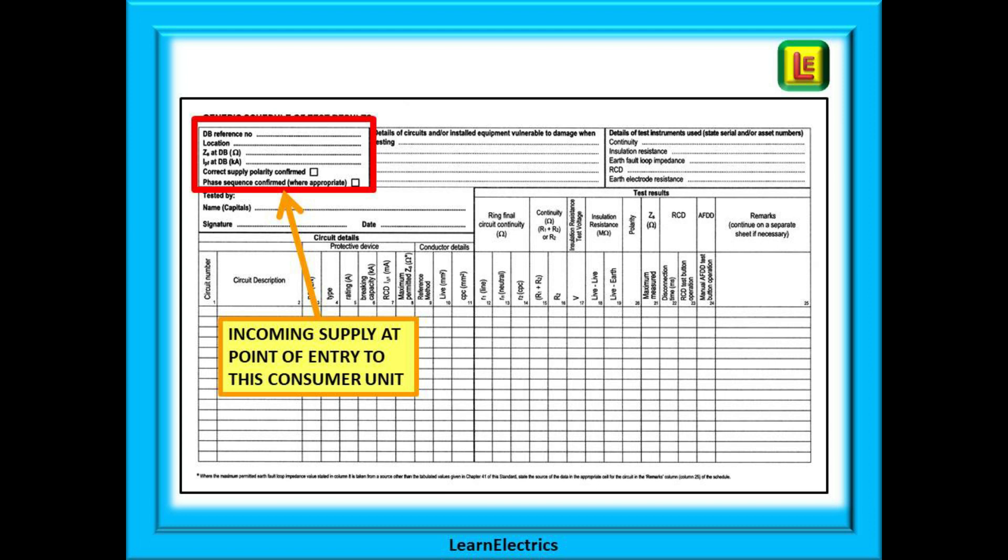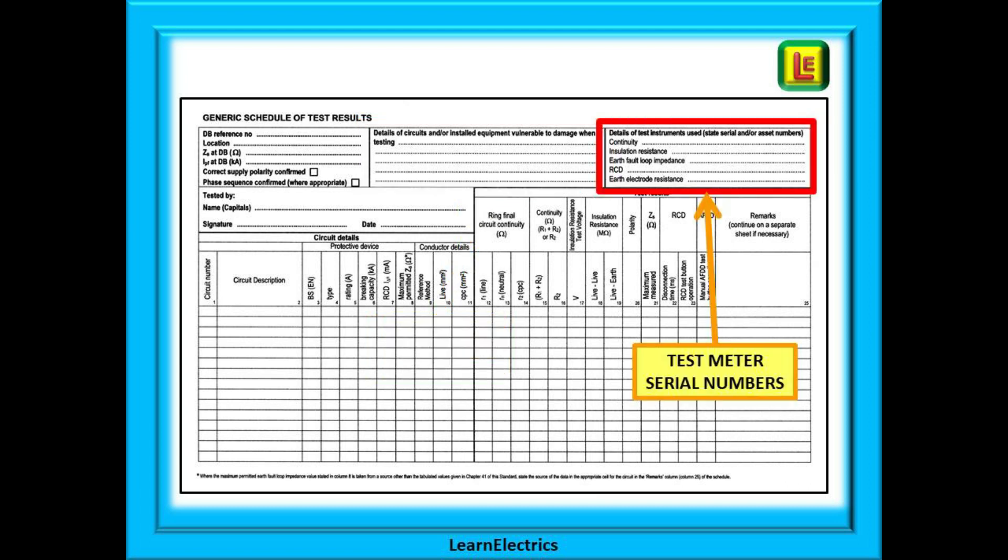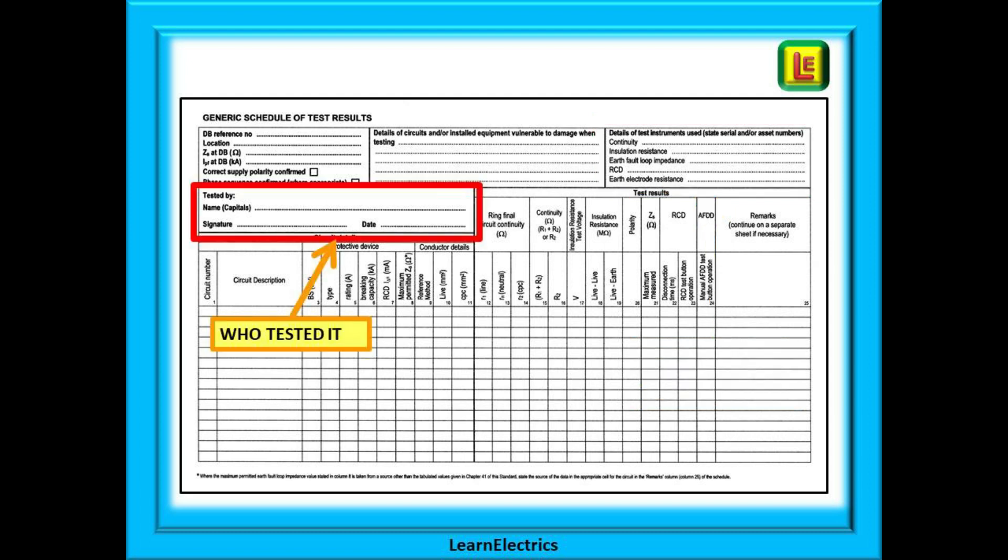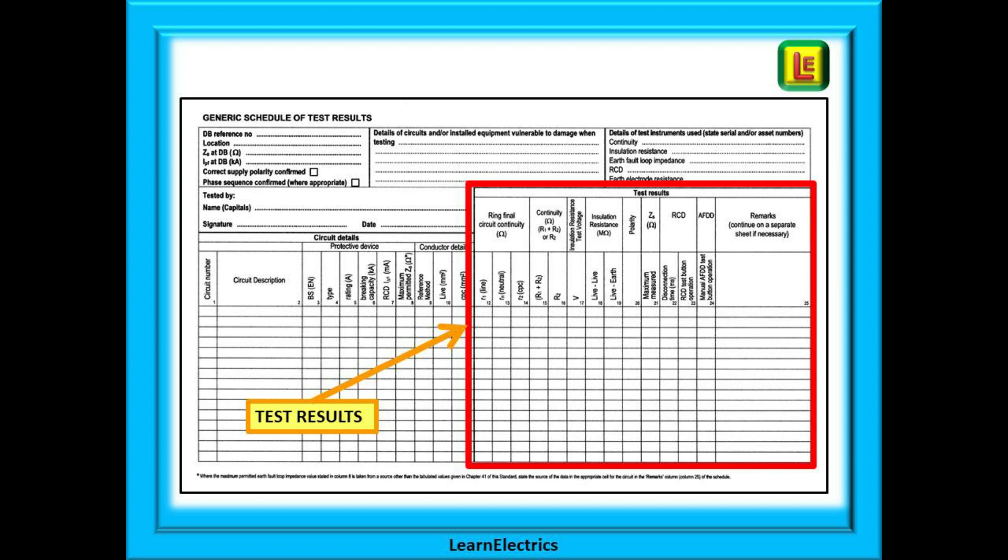I break the schedule of test results into six distinct blocks that are complete in turn. Starting at the top left we enter details of the incoming supply at the main switch to this consumer unit. In the centre we enter details of any circuits that might be susceptible to damage during testing. Top right we must enter details of the test meter or meters that were used to test the circuits on this schedule. Back to the left hand side now and a section for the name and signature of the person testing the circuits and the date that the tests were carried out. Bottom left we find a big section called circuit details with enough entry rows for a standard 12 way consumer unit. More than 12 ways will require a continuation sheet. And finally on the right another big section simply called test results.